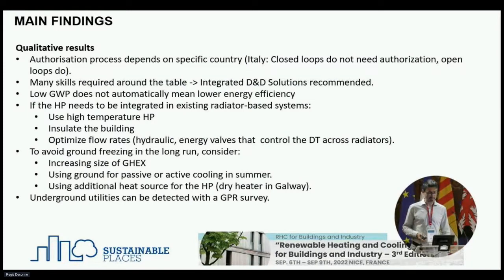And finally, with geothermal, you have the risk of freezing the ground in the long run because you're constantly extracting heat from the ground. In order to avoid it - this happens in the long run - you can increase the size of the ground source heat exchangers, increasing the cost, of course, but hereby you extract less heat per unit of space.